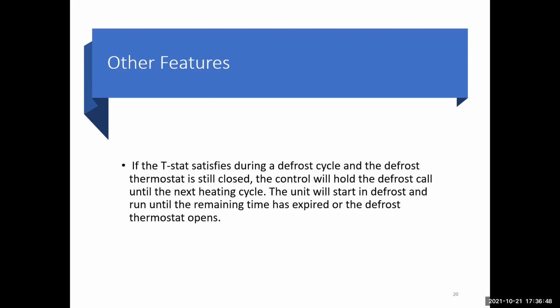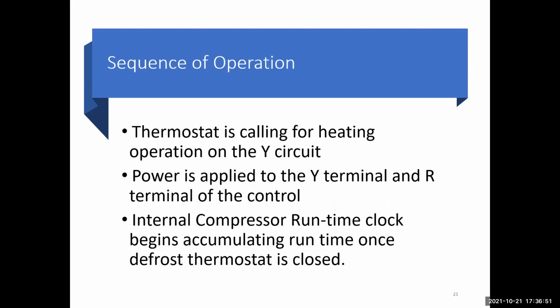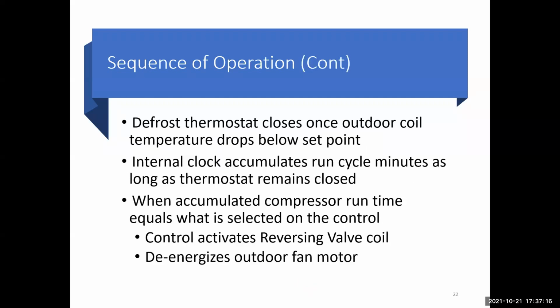Sequence of operation: the thermostat is calling for heat operation on a Y circuit. Power is supplied through the Y terminal and R terminal of the control. Internal compressor runtime clock begins. Runtime accumulates once the defrost thermostat is closed. The defrost thermostat closes once the outside temperature drops below the set point. The internal clock accumulates the running time as long as the thermostat remains closed.